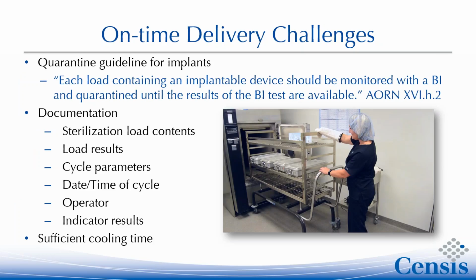For sets that contain implants, regulatory guidelines recommend that a biological indicator test be included in the sterilization load. Until that specific BI test has completed its incubation period and been read, the tray with the implant on board has to stay in quarantine—you can't rush through that step.